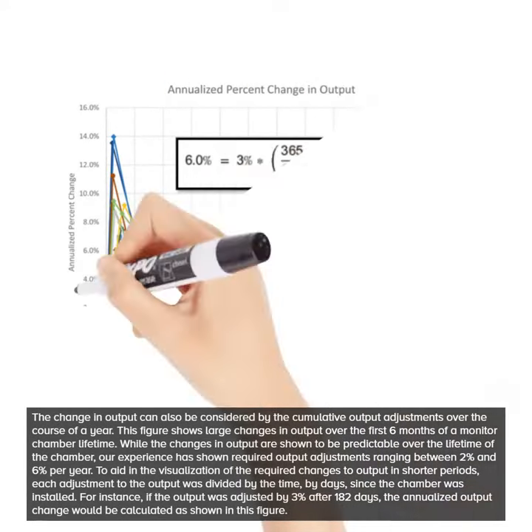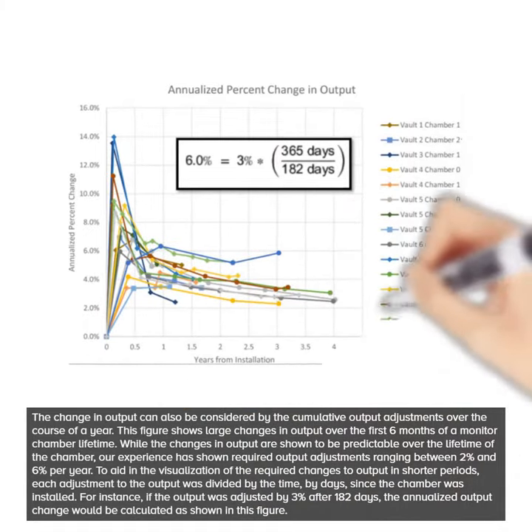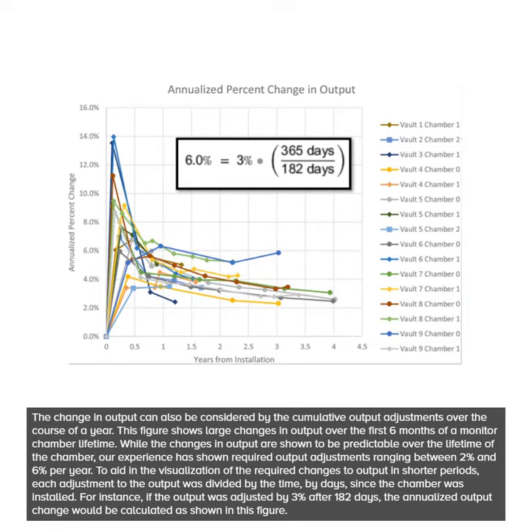The change in output can be considered by the cumulative output adjustments over the course of a year. This figure shows large changes in output over the first 6 months of a monitor chamber lifetime. While the changes in output are shown to be predictable over the lifetime of the chamber, our experience has shown required output adjustments ranging between 2% and 6% per year.